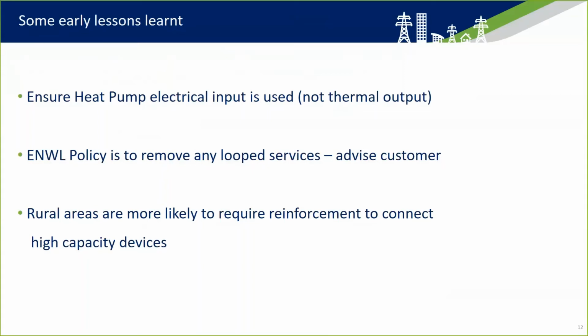Rural areas, generally the network is not as strong as urban type areas. So if you are looking to install high capacity devices in these types of areas, it's generally more likely that we may need to reinforce the network to accommodate it. Similarly, locations close to substations are better than at remote ends. So again, if we have developers who are looking to install numbers of devices in an area, it may be worth, before you apply, coming in and talking to us. So we could give advice on locations of substations if you've got the flexibility to put them in different areas.